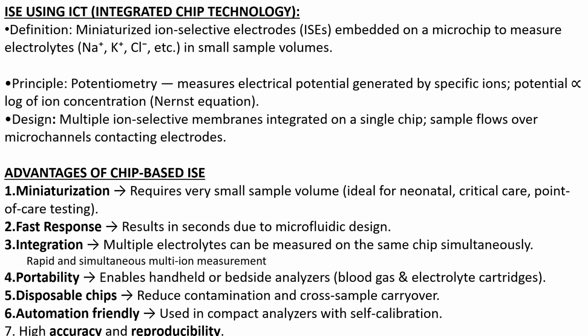Here, instead of large electrodes, miniaturized ISEs are integrated on a silicon chip. Each chip contains multiple ion selective membranes patterned side by side. This chip is inserted into the analyzer and tiny volumes of sample are enough for the measurement. The ISEs are embedded on a microchip to measure the electrolytes in small sample volumes. The principle is potentiometry. It measures the electrical potential generated by the specific ions, and the potential difference is directly proportional to the log of the ionic concentration, which is the Nernst equation.